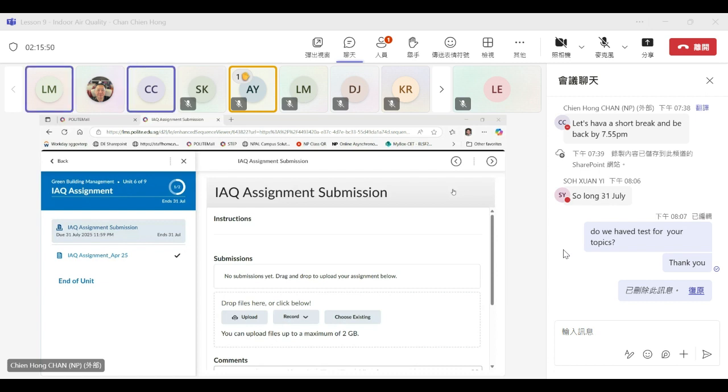Yes. Okay, the printer room is actually the first room after the issue, so that was the first stop before it goes to other places. So we suspected that was the cause. We took an anemometer to check whether the flow is too strong, whether the AHU fan was so strong that it goes right up. But when we checked the other rooms, we had 3 rooms along the same wall, and we find it very surprising that the other 2 rooms didn't have mold at all.